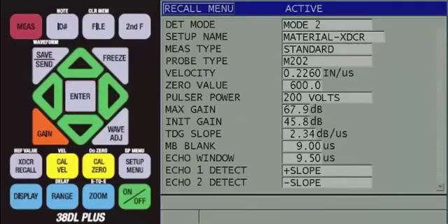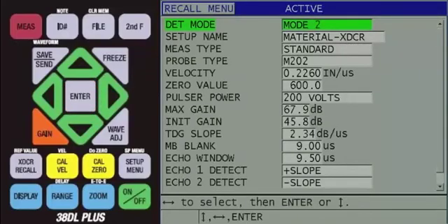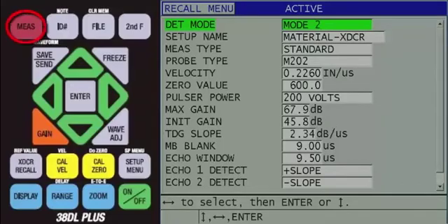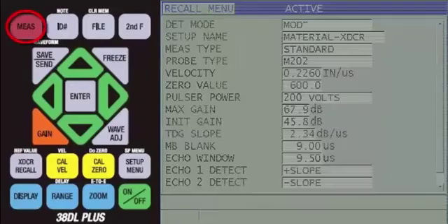The active screen, showing all the setup parameters, will now be displayed. From here, you can press the red measure key to return to the measurement screen.